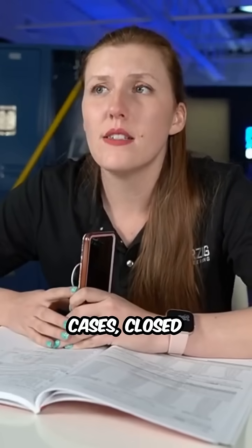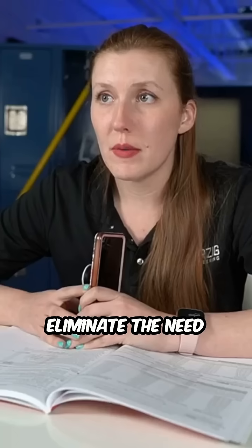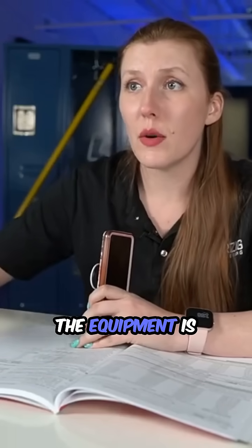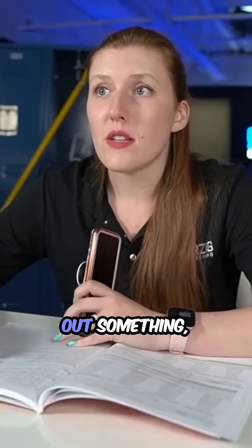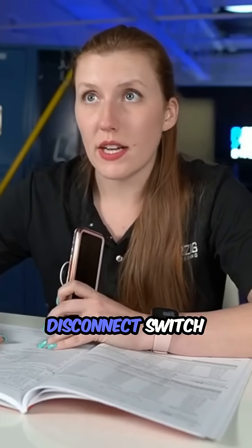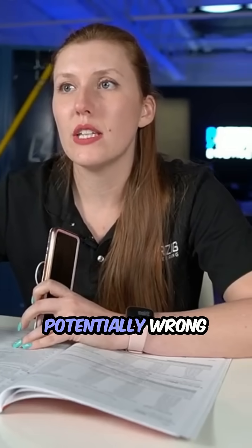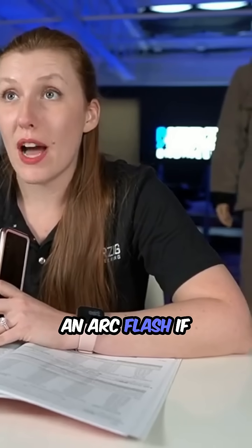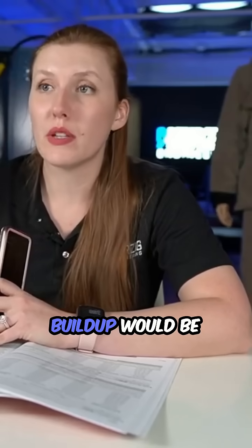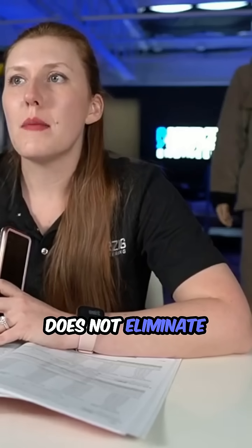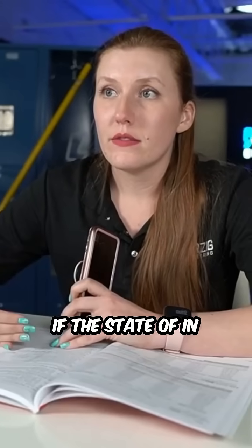130.5B, informational note, says in most cases closed doors do not provide enough protection to eliminate the need for PPE in situations in which the state of the equipment is known to readily change. So if the doors are open or closed, you're racking in or racking out something. If you're turning something on and off, like a disconnect switch, and there's something potentially wrong with it, that little door is probably not going to stop an arc flash if one were to occur in that enclosure. The pressure buildup would be enough to break that tiny little interlock switch. So doors closed does not eliminate the need for PPE if the state of equipment is known to readily change.